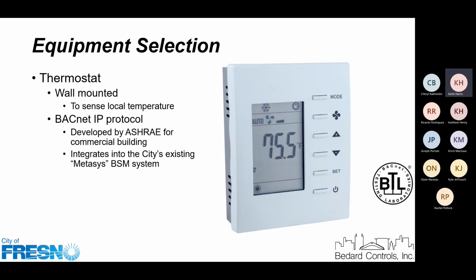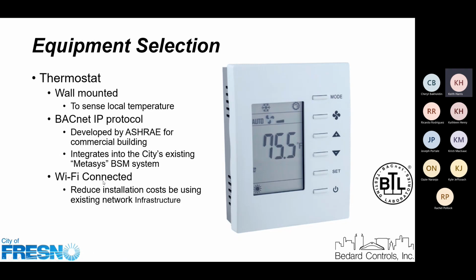What's unique about it is that it communicates back through what we call a BACnet IP protocol, meaning it actually talks back to a server that's located at City Hall or a virtual server someplace that allows us to collect data and transmit data back and forth between the thermostat, which controls the equipment, and the person interfacing with the EMS or BMS system. We do that through the infrastructure that's already in place, which is the Wi-Fi networks at most of the city's facilities. And we do that through a sub-routing technique where we bring in data to the Wi-Fi through the access point, and I have a little diagram to show you. Then it's sub-routed by your IT department back to our server, and then the people who are in charge of maintaining the HVAC equipment, providing the schedules, those types of things, can access the thermostats remotely.